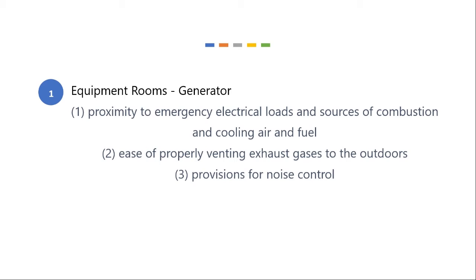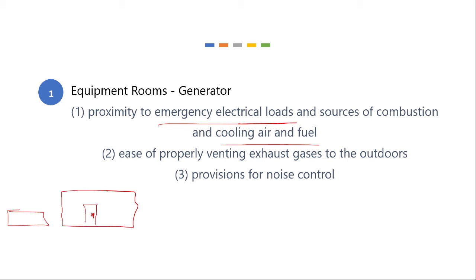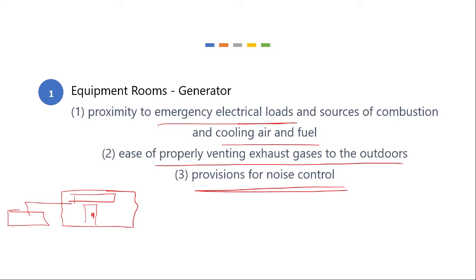We also need to have generators, and the generator should be as close to the emergency electrical load and sources of combustion, cooling air, and fuel. The generator needs to be as close as possible to what it's powering and also to its fuel supply. Maybe that's not always practical because fuel gets replenished. It may come in through a truck, so the generator might have to be outside. So you might consider a central location for your generator. You also need to be able to ventilate exhaust gases outdoors, and consider how noisy your generator is. You don't want it to be too close to the occupants.